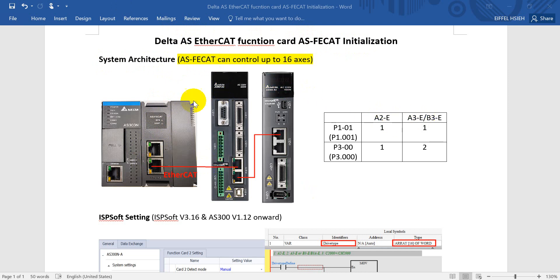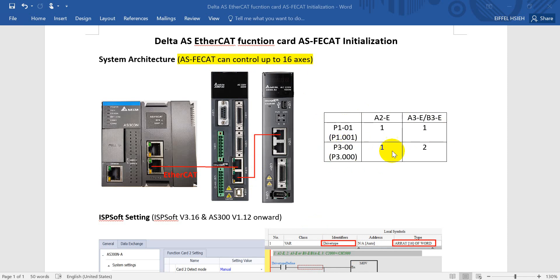For this function card you can control up to 16 axes. Here are the parameters that you have to set up for the control mode. For A2E P1-01 or A3E P1-001, this one we will set to 1, which means PR mode. Then for the station or node ID P3-00 or P3-000, this one for A2E we set 1 and A3E we set 2.